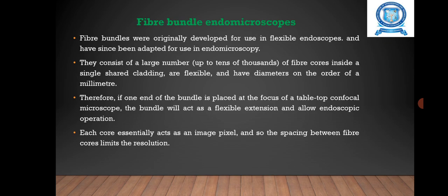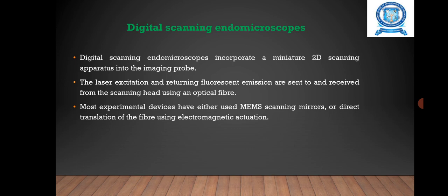The next one is distal scanning endomicroscopes. It is used to incorporate a miniature 2D scanning apparatus into the imaging probe, and the laser excitation and returning fluorescent emission are sent to and received from the scanning head using an optical fiber. Most experimental devices have used either MEMS scanning mirrors or direct translation of the fiber using electromagnetic actuation.